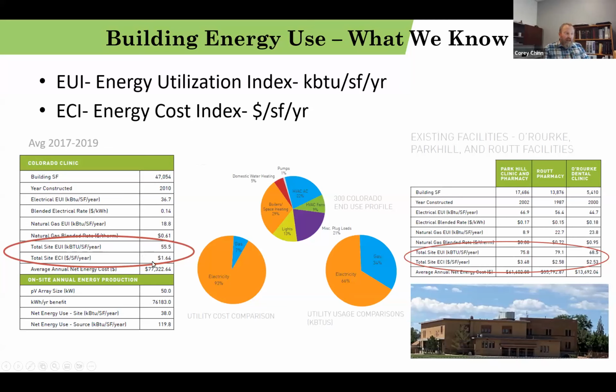So, all right, we had those three smaller clinics. The Colorado clinic was 47,000 square feet. It was constructed in 2010. It provided a great baseline facility to compare our results for this new project to. They had an EUI of 55 and a half and a site cost index of $1.64 per square foot per year. This building was operating quite well.